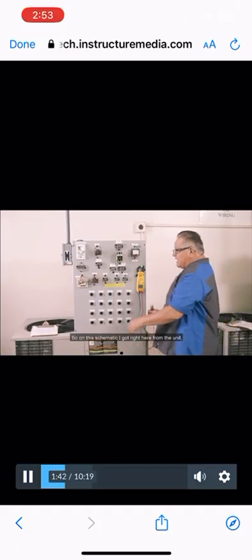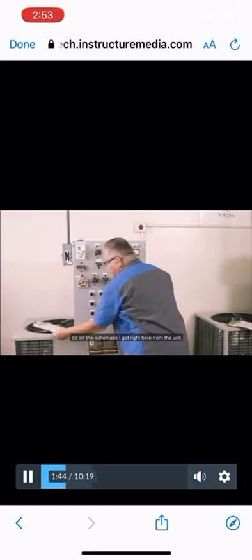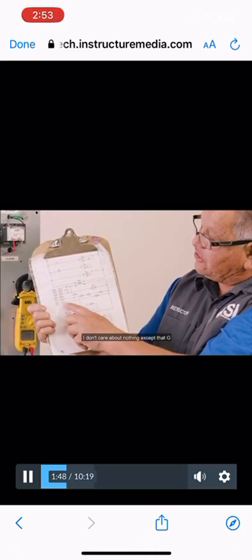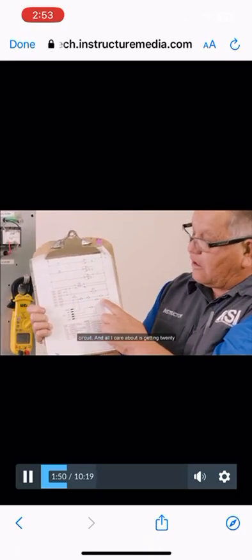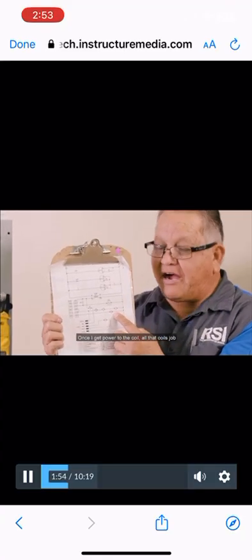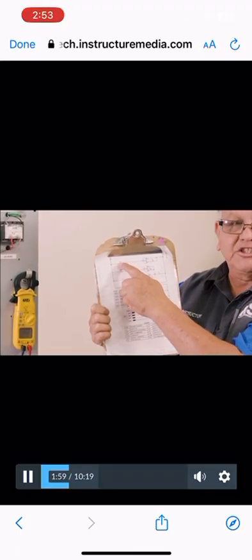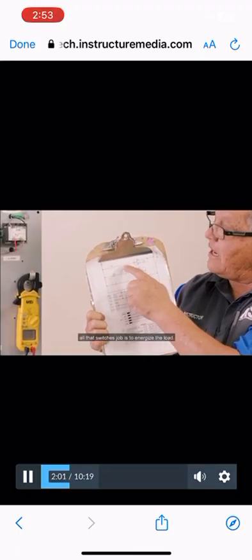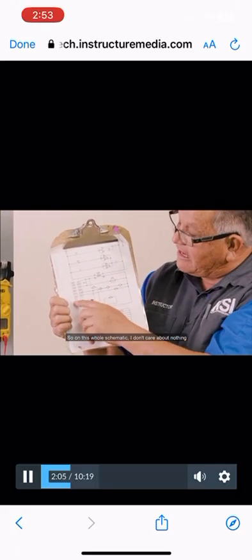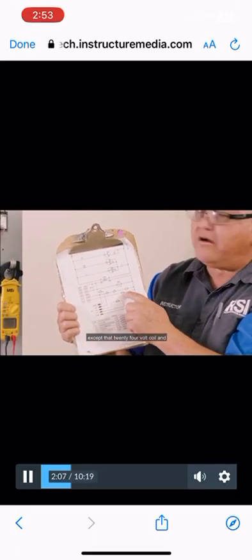So I'm calling for fan. On this schematic I got right here from the unit, I don't care about nothing except that G circuit, and all I care about is getting 24 to that coil. Once I get power to the coil, all that coil's job is to energize that switch. All that switch's job is to energize the load. So on this whole schematic, I don't care about nothing except that 24 volt coil and this circuit here.